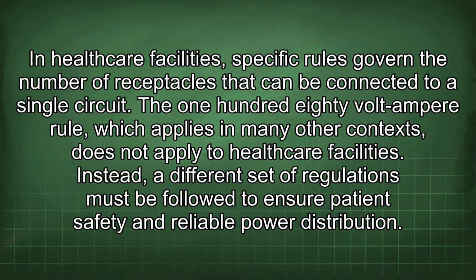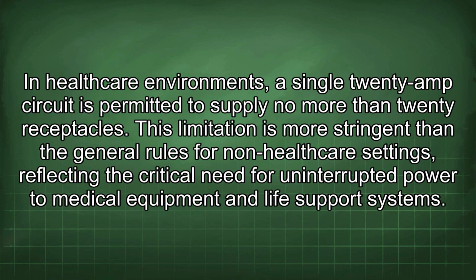In healthcare facilities, specific rules govern the number of receptacles that can be connected to a single circuit. The 180 volt-ampere rule, which applies in many other contexts, does not apply to healthcare facilities. Instead, a different set of regulations must be followed to ensure patient safety and reliable power distribution. In healthcare environments, a single 20-amp circuit is permitted to supply no more than 20 receptacles.